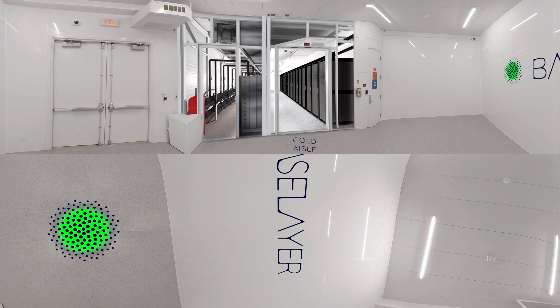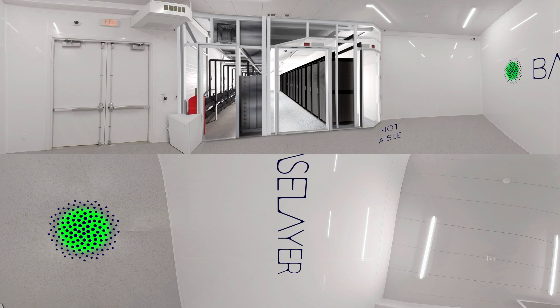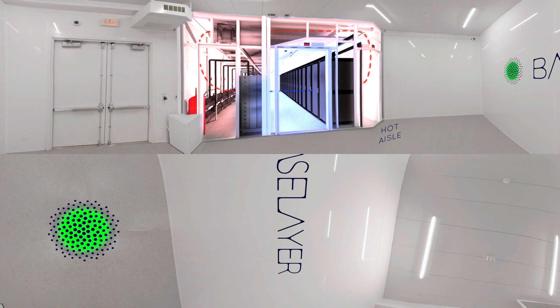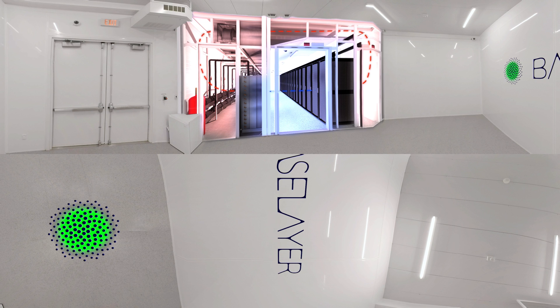So, how does the XC10 work to deliver an enterprise-level data center? A pressurized plenum is created between the cooling and IT blocks. Conditioned filtered air moves through the openings at one end of the IT block and flows through the IT equipment. It's returned through a pressurized top air return. Once in the cooling block, the returned air moves through several heat exchange coils, where heat transfer takes place and the cycle starts again.